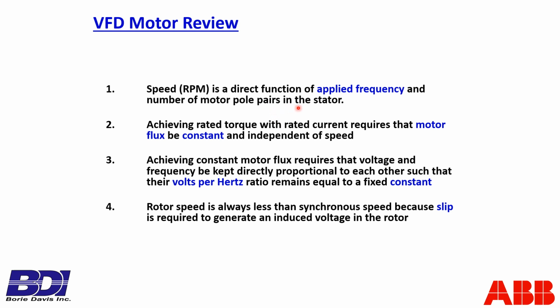So the speed is a direct function of the applied frequency and the number of motor poles. Achieving the rated torque with rated current requires that the motor flux be constant and independent of speed, constant torque. Achieving constant motor flux requires the voltage and frequency be kept directly proportional to each other. That's your volts per hertz, and that remains equal to a fixed constant.